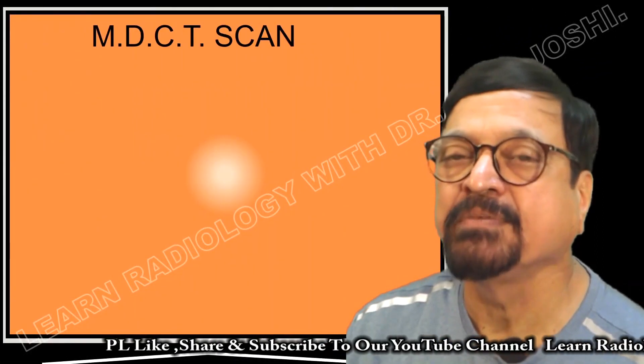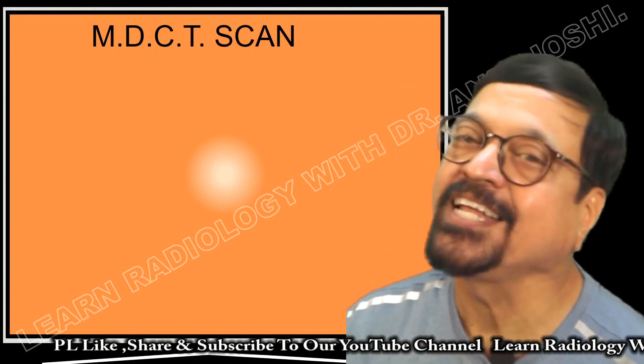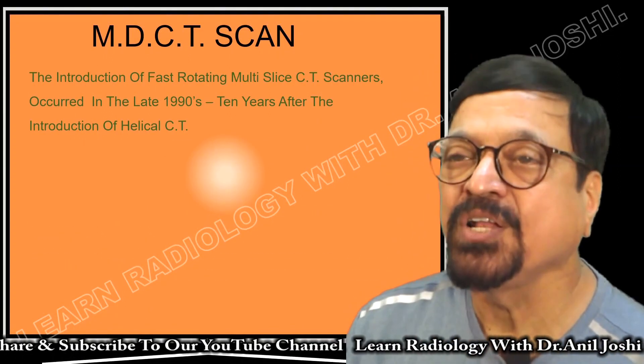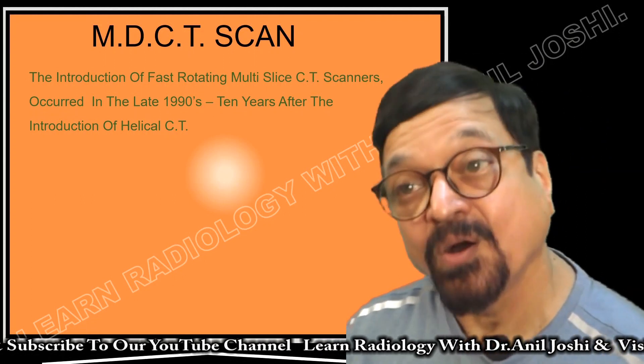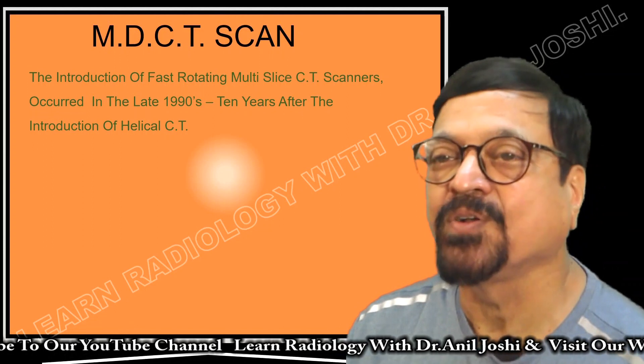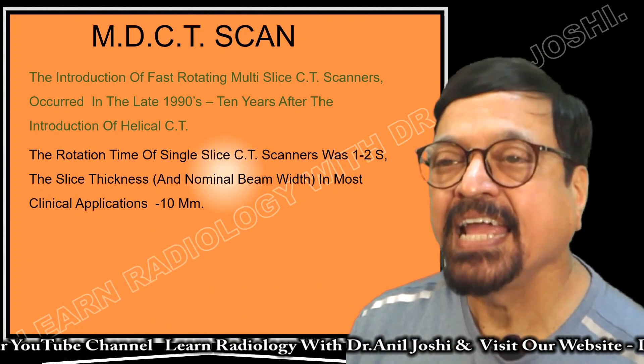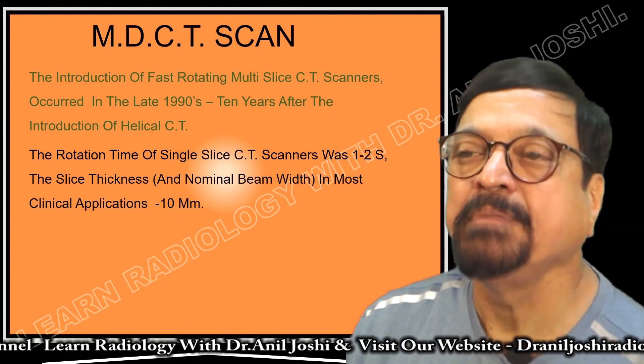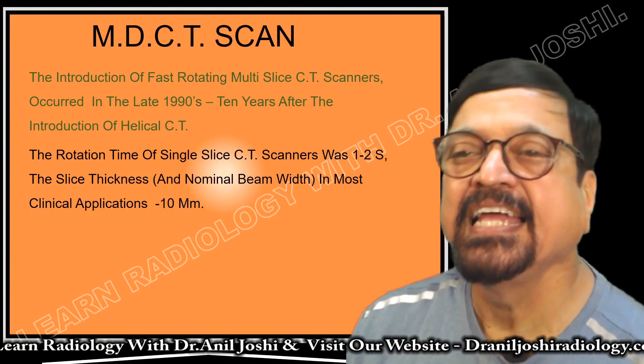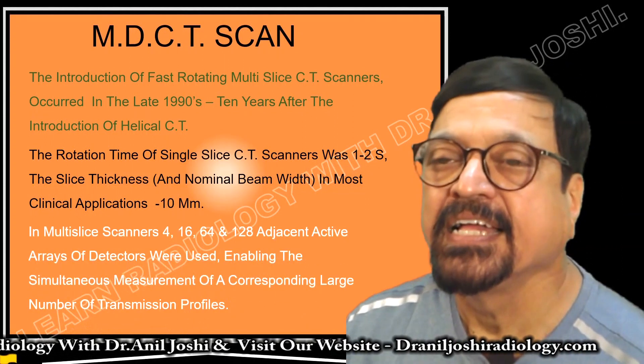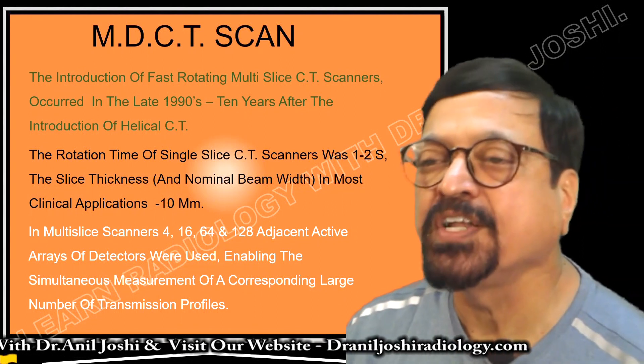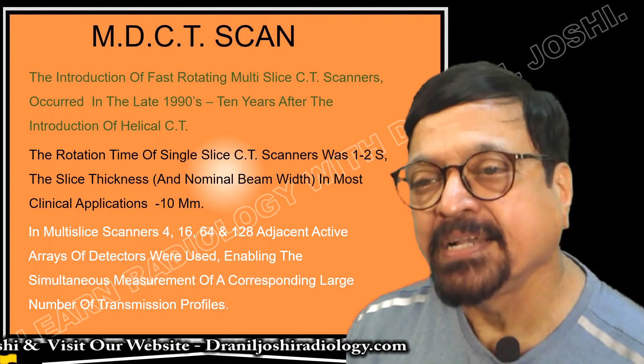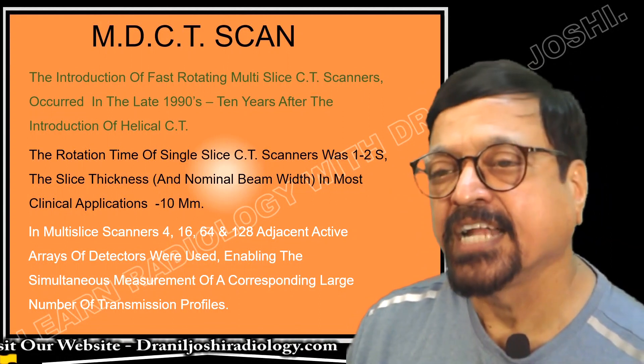These two differences make it faster, better, good for reconstruction, and good for the patient because we don't need as much patient cooperation. The introduction of fast rotating multi-slice CT scanners occurred in the late 1990s, ten years after the introduction of helical CT. The rotational time of the single-slice CT scanner was 1 to 2 seconds, with a slice thickness and beam width of around 10 mm in clinical application. In multi-slice scanners, 4, 16, 64, and 128 adjacent active arrays of detectors were used, enabling simultaneous measurement of a large number of transmission profiles.